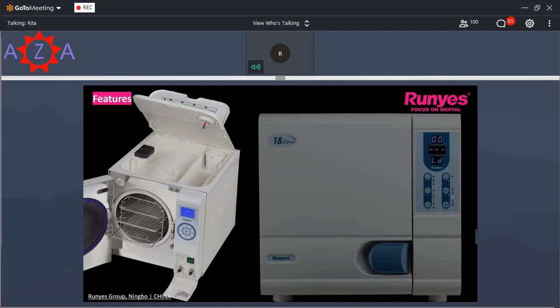In the waste water and the clean water tanks, we install water level sensors. So the machine will alarm you to drain off water or add water. If the waste water level is too high, it will remind you to drain off. If the clean water level is too low, it will remind you to fill water. And we also install a water quality sensor in the clean water tank to detect the water quality. According to the standards, all autoclaves must use qualified water. So for our autoclave, only use distilled water. If the water is not qualified, the machine will alarm and cannot work properly. So this is the water tank.